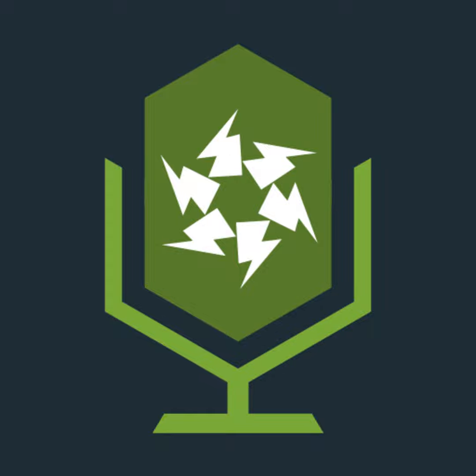Nothing else that's really worth mentioning in 422. There's a mention with luminaires and equipment. It says it'll be appropriate for the location. That makes sense. But selection and erection is very important. Provide an enclosure with a degree of protection of at least IP4X, or if there's dust present, IP5X, and if there's electrically conductive dust, IP6X. These are obviously the dust-related IP ratings. We'll refer to those as we get to chapter 52, where we look at external influences again. But your understanding of IP codes shouldn't be much of a problem, because we're going to use them a lot, especially in part 7.